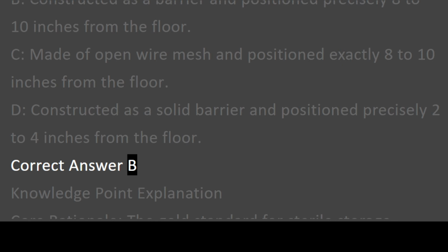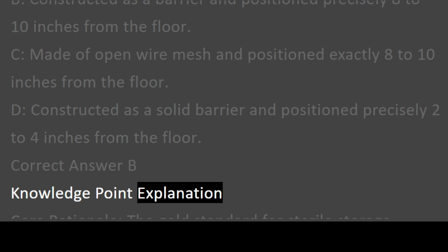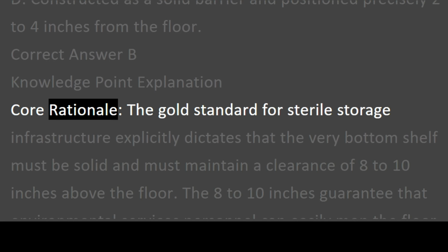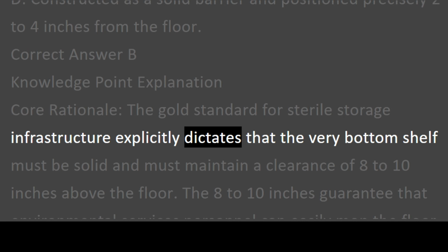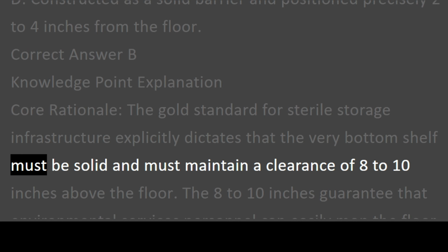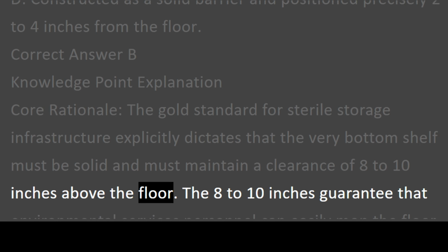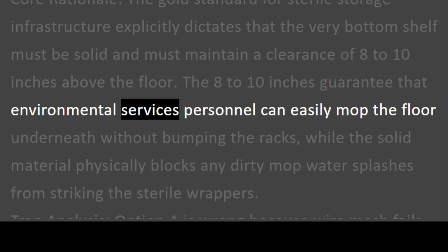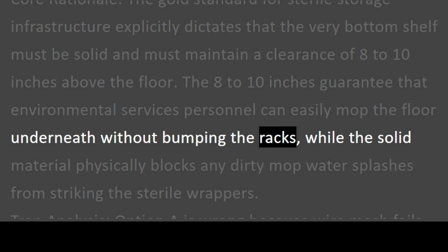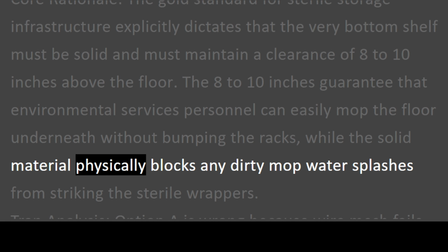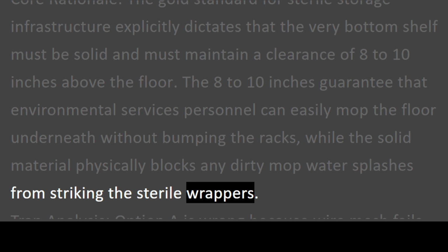Correct answer B. Knowledge point explanation. Core rationale. The gold standard for sterile storage infrastructure explicitly dictates that the very bottom shelf must be solid and must maintain a clearance of 8 to 10 inches above the floor. The 8 to 10 inches guarantee that environmental services personnel can easily mop the floor underneath without bumping the racks, while the solid material physically blocks any dirty mop water splashes from striking the sterile wrappers.